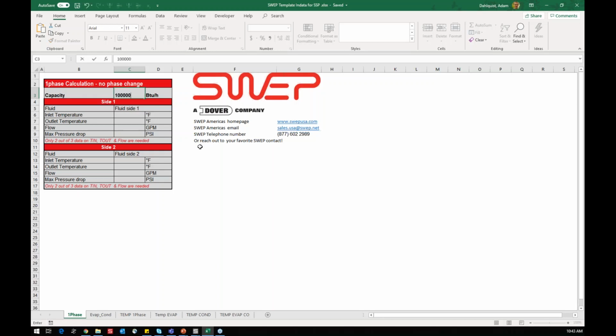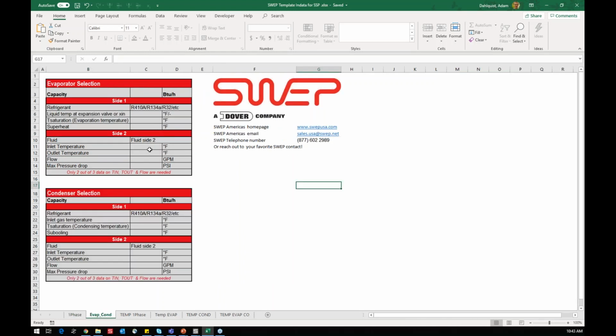Say we have 100,000 BTUs, we have 50 degrees in and 60 degrees out, whatever, right? And we have 5 GPM. This is actually too much data. If we have the BTUs, temperatures, and flows, the system is over-specified, and that is why we have this. Don't give us all three, only 2 of the 3. The same for the evaporator condenser. Here, of course, we are looking at the liquid temperature before the expansion valve in an evaporator, or the evaporation temperature. For a condenser, we would like to have the gas temperature or the discharge temperature from the compressor, and then the condensing temperature, etc.